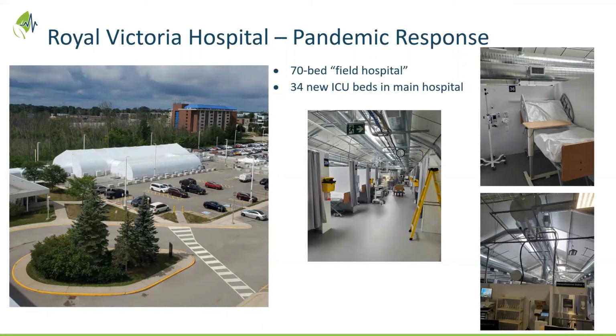With the situation around COVID, there was a big need to look at negative pressure areas, since our ICU could be surged at some point for patients on ventilators. I looked at what we could do, and nearby our ICU was the endoscopy area, which is fed off its own independent air handling unit. I changed that from recirculation to 100% outside air, fitting a couple of VFDs to control the speed. We got a balancing company in to convert the entire area into negative pressure while keeping a positive core for the sterile area, and it worked really well. It inadvertently created energy savings by reducing the motor speeds with these drives, and gave us an extra 34 ICU beds if needed.